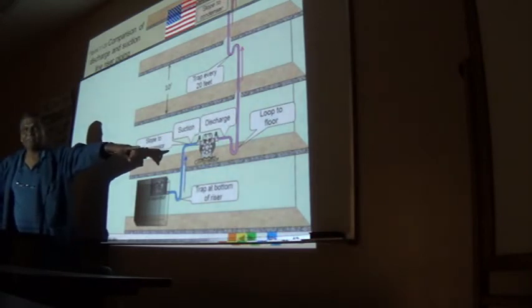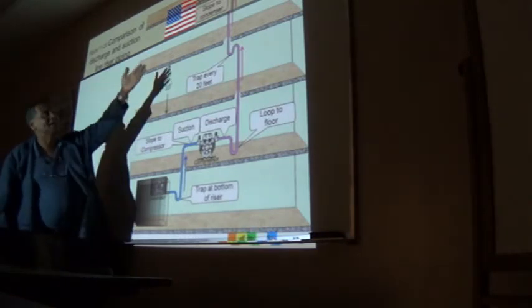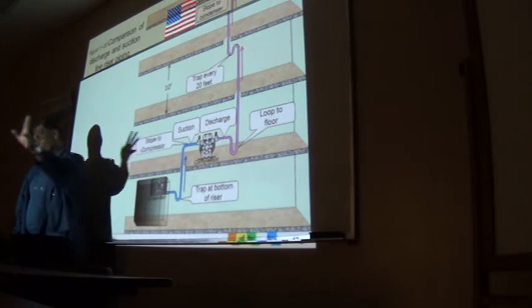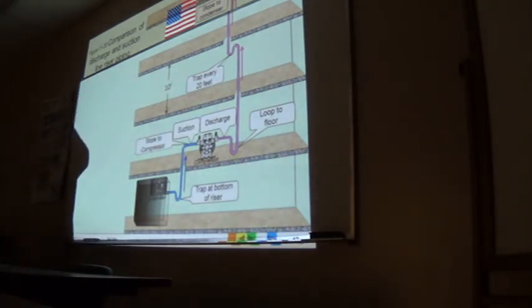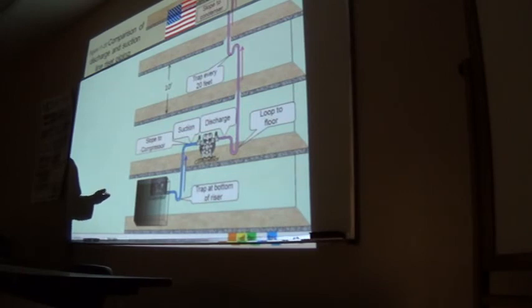So four and three, seven, seven, seven, that's like 50 feet of straight run. Same with fittings. Which, you know, that defeats the purpose of buying a line set and you're just going to increase the load on the system. And a lot of us don't really think about it. We will size the system three-quarter horsepower. And then you put all these fittings, which give you the additional length. And now, to compensate for that, we had needed to up that horsepower rating a little more. Because you're already upping it 25 percent. So you didn't up it to take care of the bends, you kind of get screwed in the line. But they get screwed. Yes, because you're never going to come down the temperature.